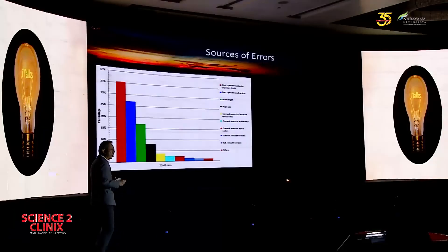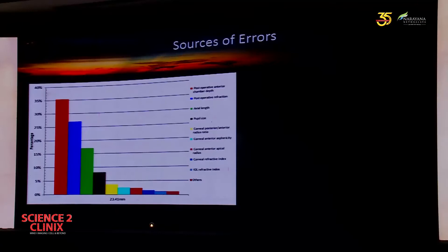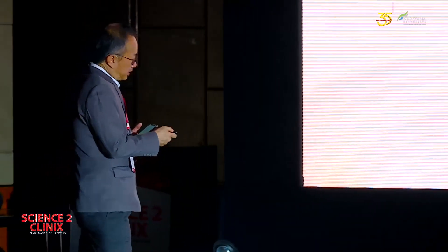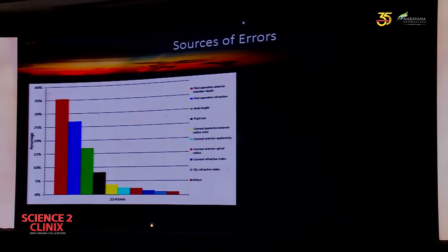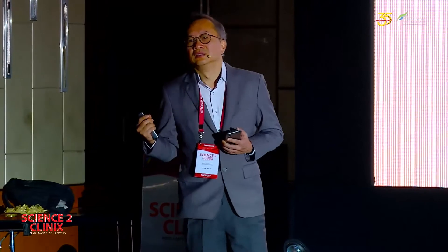No matter how good the machine is, there are still sources of errors. The humidity, ambient lighting, and temperature of the environment will affect the measurement. That's why we strongly recommend that at the beginning of the day, before your first patient, always calibrate your biometers. Formula was historically the biggest culprit, but today formulas are a lot better — this was before EVO and Barrett. Refraction is still very subjective and still varies. George Waring said the refraction varies by half a diopter every different day, so this is something you must take into consideration.